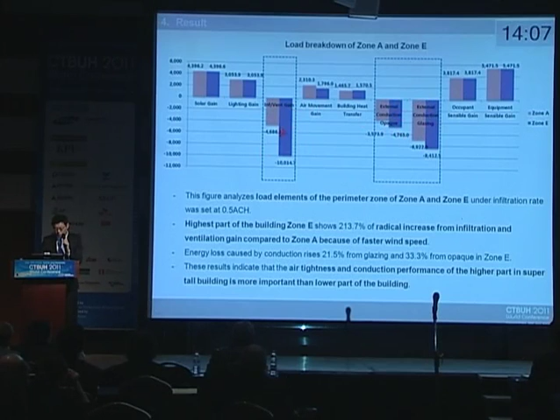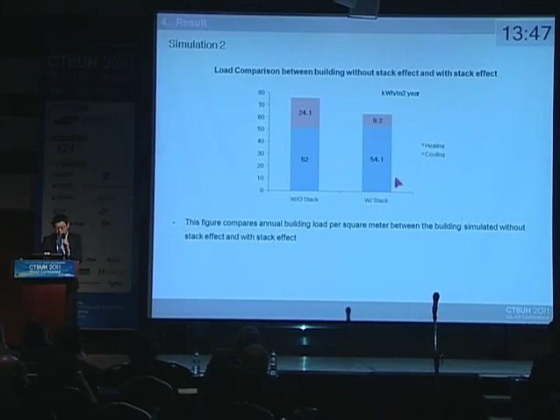And let's move on to simulation 2, which is knowing how the stack effect affects the building cooling and heating load. This one is not considering the stack effect, just like a normal simulation. And this one is considering the stack effect. And it also shows a big difference. And according to the height, this one is a 40-story building, this one is 120 stories, and this one is a 200-story building. And it shows very big differences according to the stack effect.